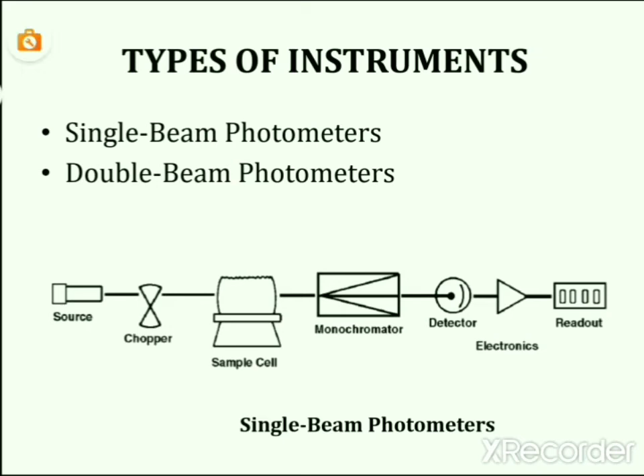An alternate photometer configuration is known as double beam instrument. It uses additional optics to divide the light from the lamp into a sample beam and a reference beam. Sample beam is directed towards the sample cell. Reference beam is directed towards the reference sample.